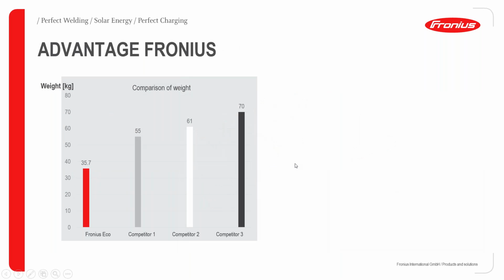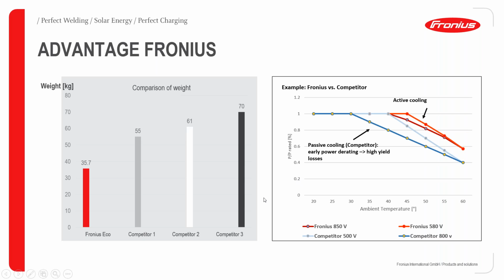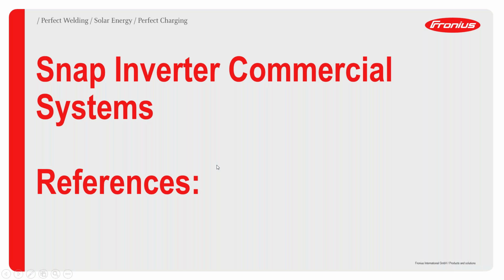all with their respective specifications. So the advantage that Fronius provides is that in terms of power produced with respect to weight, we have the advantage here. As you can see, this is a comparison between the Fronius Eco and 3 other competitors, all producing the same amount of power. Looking at the power production per weight, Fronius has the advantage because it weighs way less, at some point half of the weight of some of our competitors. This proves how much work we put into our inverter to make sure that you have the best possible inverter in both size and output capabilities. Yes, we've talked about the active cooling. Let's now look at references, like I promised you.